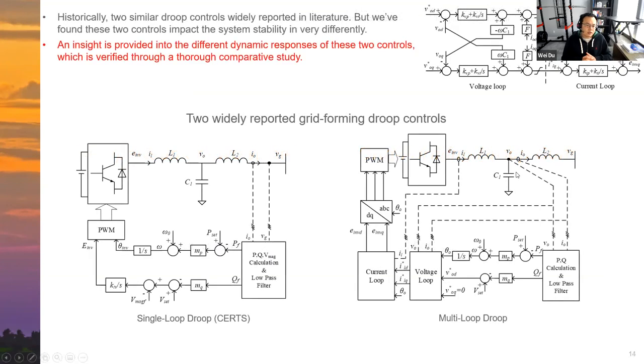So here this slide shows two widely reported grid-forming droop controls. When I was a student, I think they were widely reported in the literature, and they still are now. At the left side is the very simple CERTS droop control. We call it the single loop droop control. You can see that the controller directly regulates the magnitude and the phase angle of the modulation waveform. There are no inner voltage or current loops. And then at the right side, it's also called droop control, but other than this PF and QV droop control, there are some additional inner voltage loop and current loops in this controller.